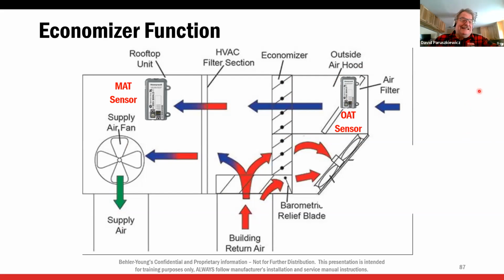What if it's today? What if you turn this air conditioner on today? It says, hey, it's 16 degrees outside. We can cool with this all day. So I open these dampers and that cold air starts coming in and it dumps down the supply, 16 degree air. What happens when somebody's sitting under that diffuser at their desk, 16 degree air dumping in? It's not comfortable. So now we have a mixed air sensor right here. So what's going to happen is that mixed air sensor is going to modulate these dampers to keep this mixed air from getting below 55 degrees. And it'll modulate until we cool the space, then these dampers close.